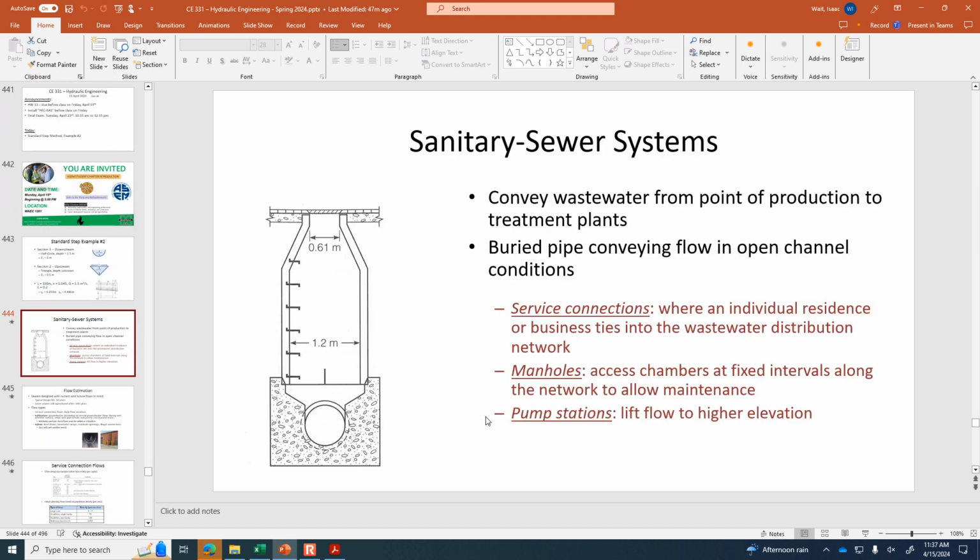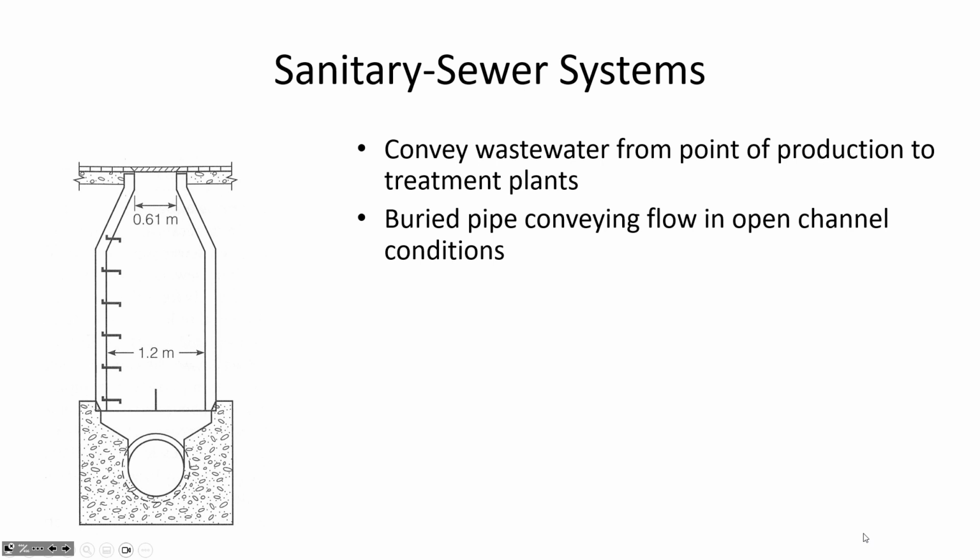All right, so now let's talk about sewers. And sewers are interesting for two main reasons. One is that there's a biological component to what's going on. We don't talk about biology much in hydraulic engineering, but this is a rare case where the hydraulic engineer has to know a little bit about the water quality and the effect that it could have on the infrastructure. Because wastewater supports microbial respiration, and one of the constituents in wastewater typically is sulfur. And the bacteria that are breaking down biochemical oxygen demand in wastewater are also reducing sulfur, and it forms a corrosive and poisonous gas known as hydrogen sulfide.